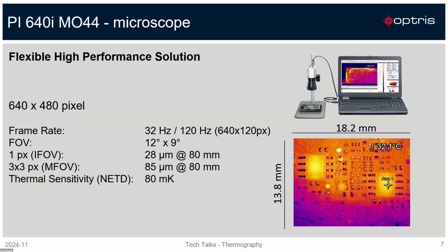Yeah, we provide this also with a 12 degree × 9 degree optics. And here you can go down to 28 micron at a distance of 80 millimeter. And you have here a horizontal field of view of 18 millimeter and a vertical field of view of 13 millimeters. The thermal sensitivity here is also 80 millikelvin.